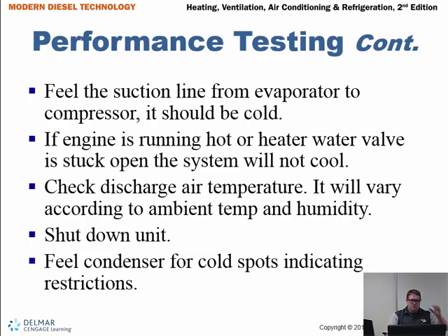will not cool. So here's another one of those things that we need to talk about. Some systems are very dependent on making sure that hot water valve is off, and we've talked about that in class. A lot of systems have a vacuum operated shut-off valve, hot water shut-off valve, and that needs to work in order for the system to work properly.